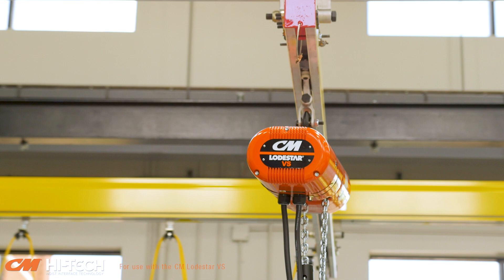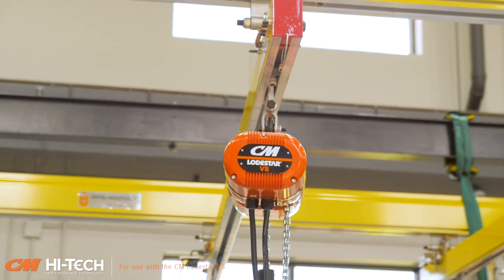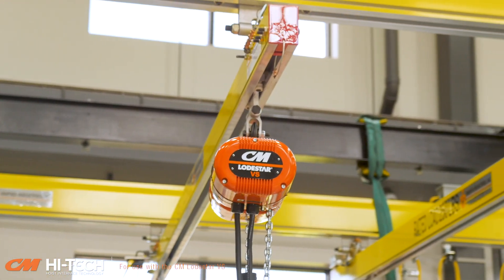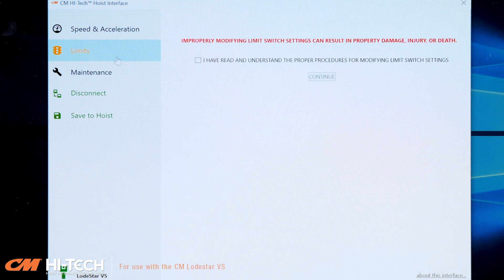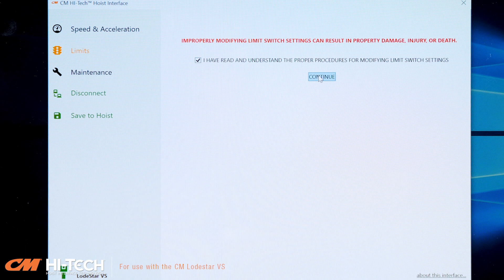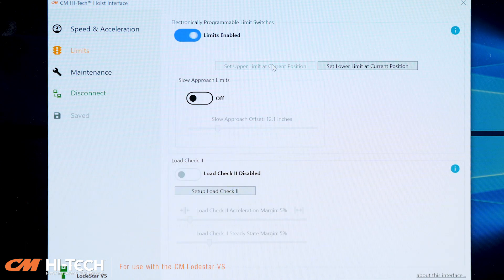Check the hoist manual for recommended minimum clearance. Once the hook is in position, return to the CM Hi-Tech interface. Go to the Limits section of the interface and review the safety acknowledgement. Then click the Set Upper Limit at Current Position button in the interface.